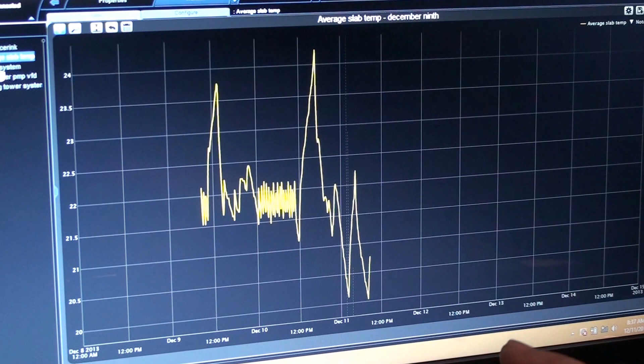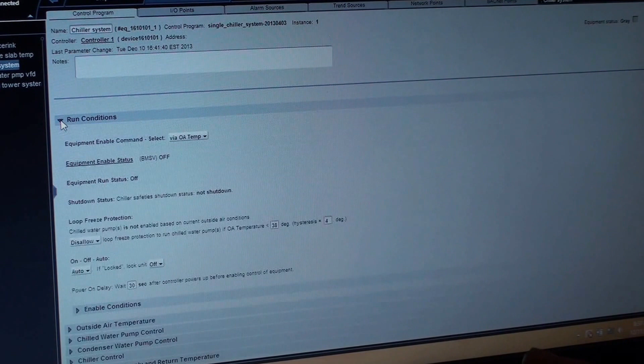20.17 degrees is quite cold, so what I'm going to do is lower the differential to 0.25 degrees. To do that, we come up to chiller system. We'll go back up here to properties. We'll go back to run condition. Come down here to enable condition. We scroll down to our set point, and next to that is a 2 degree differential.